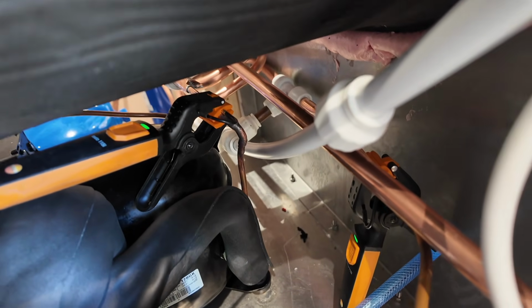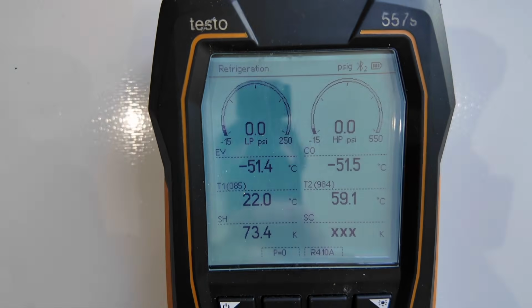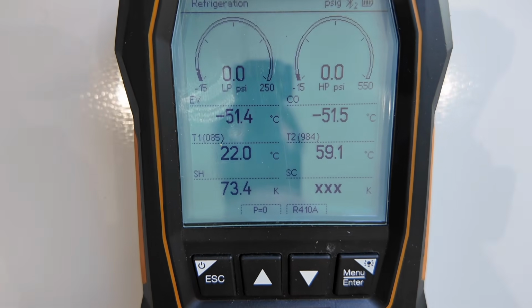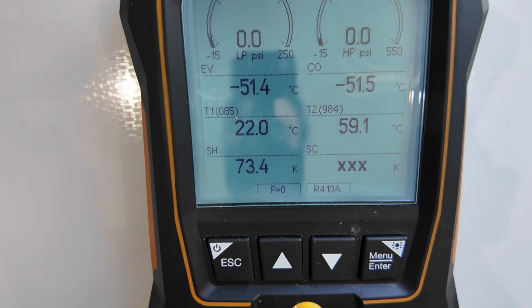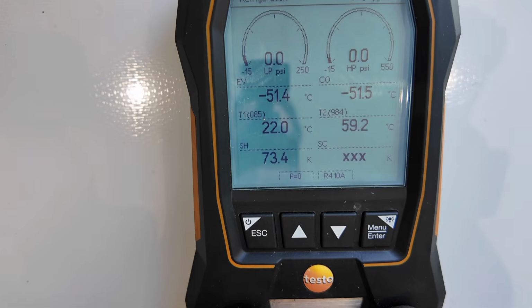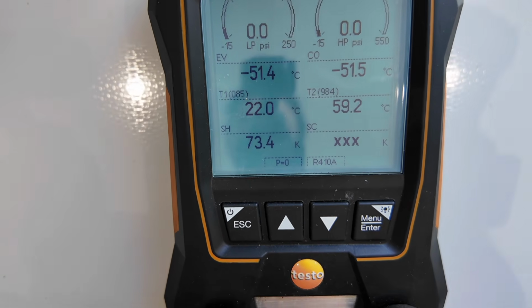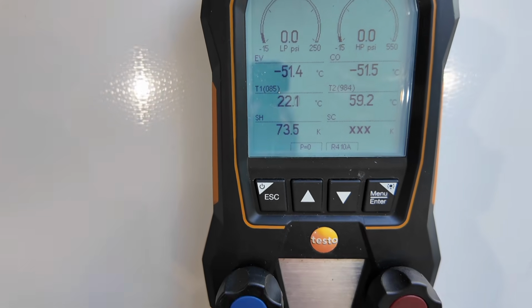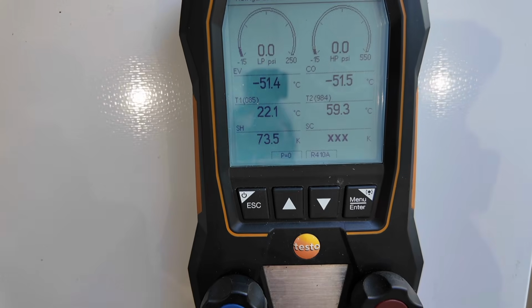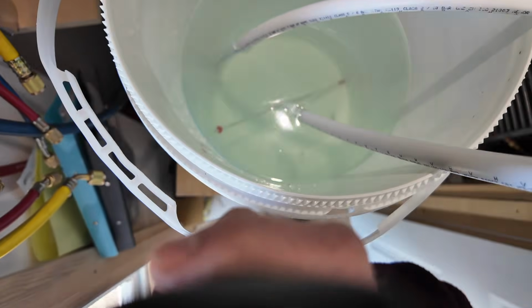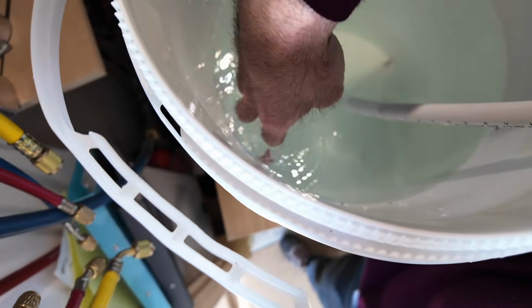So I've got two temperature probes on the system now, on the discharge line going in and coming out of the heat exchanger. It says about 59 going in, but that's probably more like 70 - the probes aren't very accurate unless they're clamped on tight. The 22 is probably more realistic for the outlet, so that's quite a good heat transfer considering it's only a homemade heat exchanger, especially given the water loses heat through all the copper pipe on its way to the bucket, and around the bucket itself.